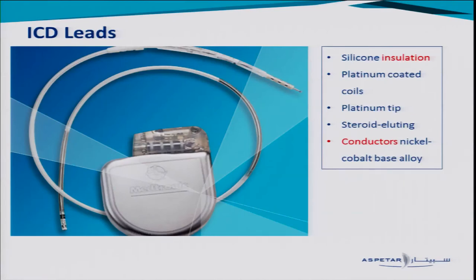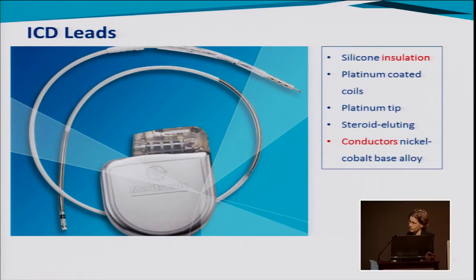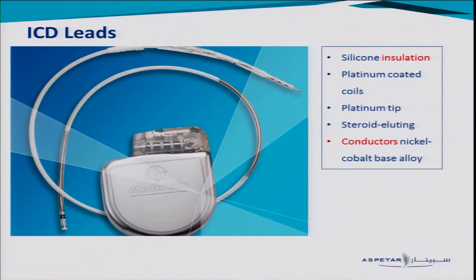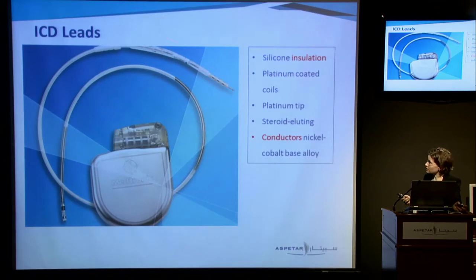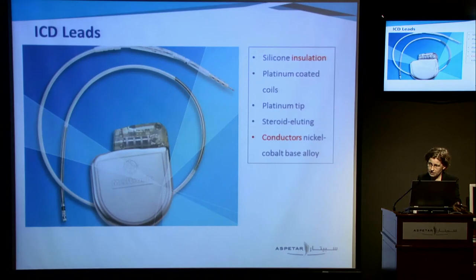It's not just a device — there's a lead as well, and really the lead is the Achilles heel of the whole system. If the device is going to fail, it's usually the lead that's the problem. It has silicone insulation and platinum-coated coils, and these coils are the places on the lead where the shock is delivered. You can have one coil distally in the right ventricle, or two coils where the more proximal coil sits in the superior vena cava. The conductors run down the middle of the lead and deliver the pacing impulses.